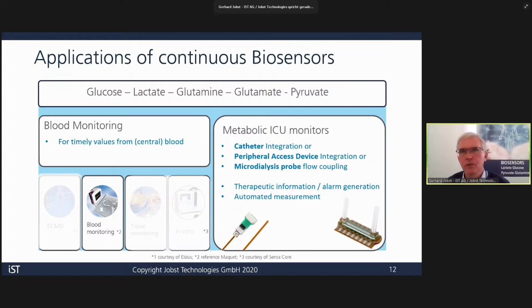which allows a variety of integration scenarios to realize metabolic ICU monitors, and I've just picked out 3 of them. One is direct catheter integration, as we have seen in the past from Edwards Lifesciences in the GlucoClear. This was a glucose sensor only, integrated to a catheter, withdrawn from the market soon after it was launched. An alternative integration scenario is integration in or through a peripheral access device, what simply stands for the well-known Venflon, that is typically put to almost any hospital patient staying for a couple of days, or through a flow coupling to a microdialysis probe. And again, of course, with the purpose of providing therapeutic information, alarm generation, and having automated measurement.